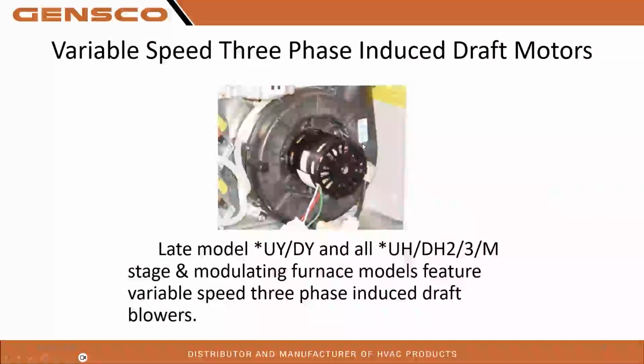So variable speed, three-phase induced draft motors. This is the big confusion in the field with guys that haven't seen this legacy product or even never worked on this Trane unit, because usually the conversation I have with the person on the phone is, well, no, this is not a three-phase unit because it's a 120 volt residential unit. Well, that motor is three-phase. Okay. We did have a square body one. So this motor you see in this picture is a round body. We did have an older one that was square in variable speed.